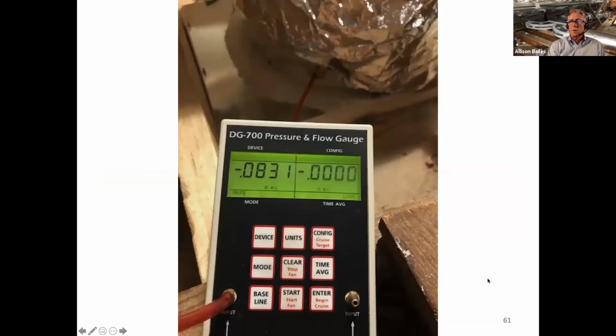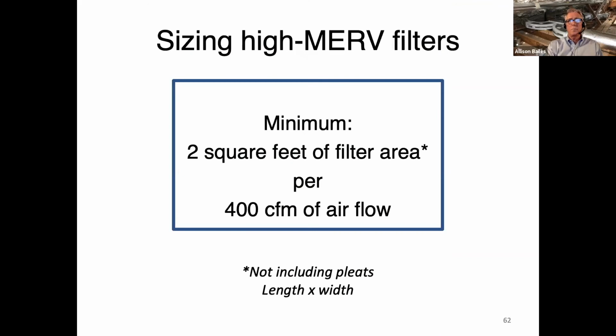So when I first installed this, I was getting a pressure drop across the filters of 0.08 inch of water column, which is pretty good. ACCA says to use 0.1 inch of water column for pressure drops across filters, and they're talking about the MERV 2 filters that are usually installed. So I'm getting 0.08 with a MERV 13 filter, but I was not happy with that because here's the problem. Well, I'll get to the problem in a minute. I'll show you how I improved it.